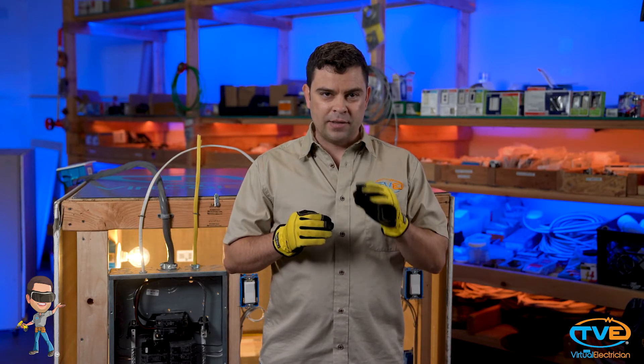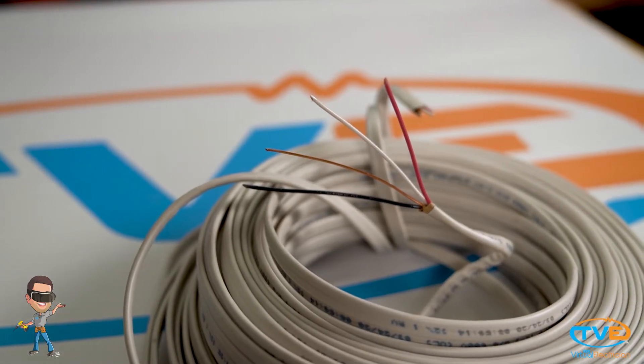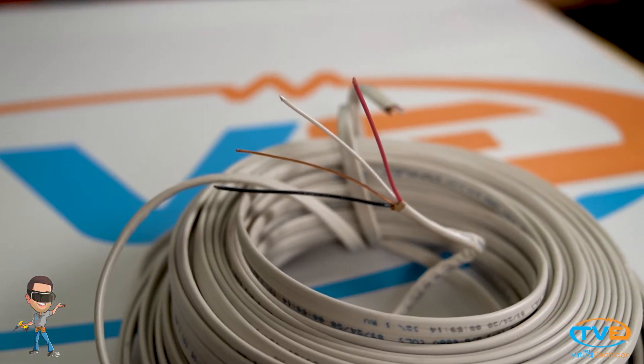That's everything you need to run a safe grounded circuit. If you look inside the jacket of a 14-3 wire, there are all those wires plus a red wire. That extra wire can be used in different ways. If you want to turn lights on from different locations, you need to run 14-3 wire because you need traveler wires. You can also use 14-3 wire if you are installing multi-wire branch circuits, meaning you are using the black wire for phase A and the red wire for phase B, and you are sharing the neutral wire.